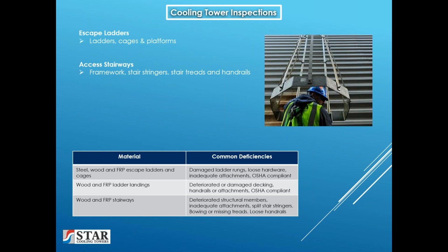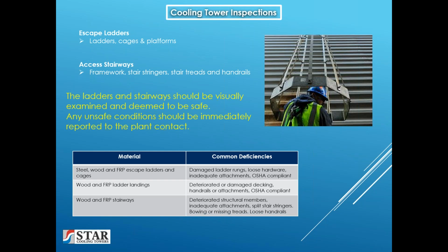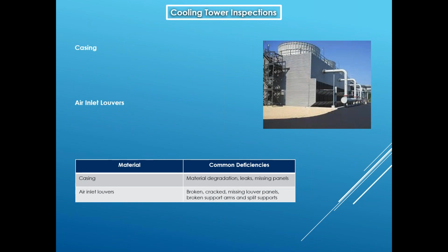We'd look at the stairways and escape ladders, any access to the tower, and the ladders and stairways should be visually examined and deemed to be safe. And any unsafe conditions should be immediately reported to the plant contact. The casing or the siding on the exterior of the cooling tower acts to contain water inside the tower, and it provides an air plenum for the fan, and transmits wind loads to the framework.